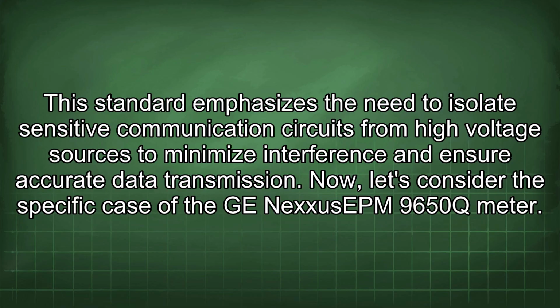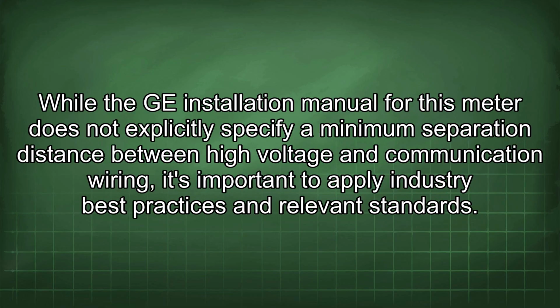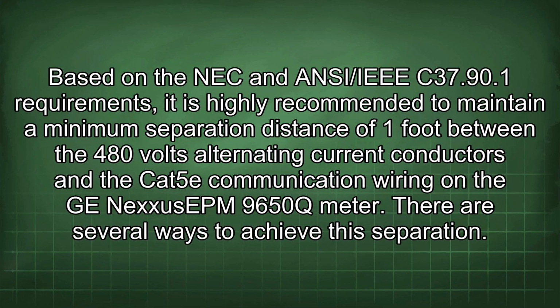Now, let's consider the specific case of the GE NexxusEPM 9650Q meter. While the GE installation manual for this meter does not explicitly specify a minimum separation distance between high voltage and communication wiring, it's important to apply industry best practices and relevant standards. Based on the NEC and ANSI/IEEE C37.90.1 requirements, it is highly recommended to maintain a minimum separation distance of 1 foot between the 480 volts alternating current conductors and the Cat5e communication wiring on the GE NexxusEPM 9650Q meter.